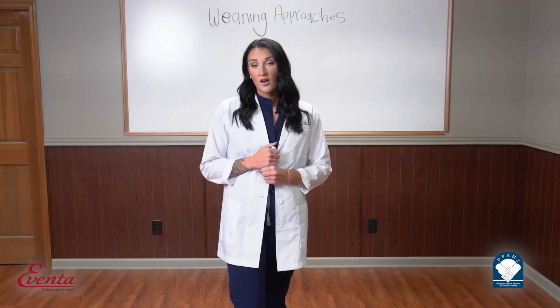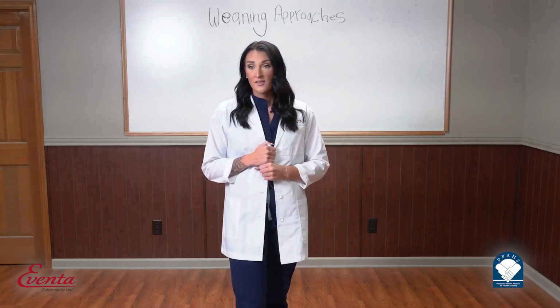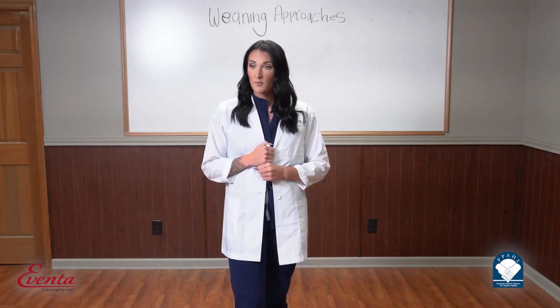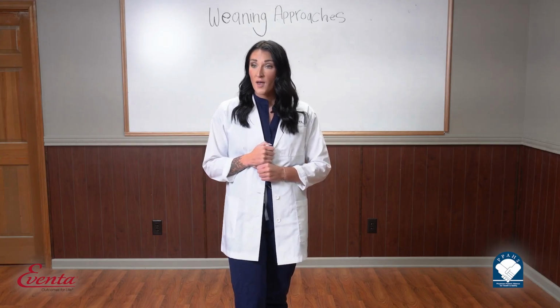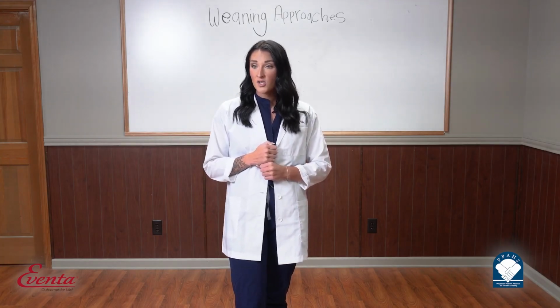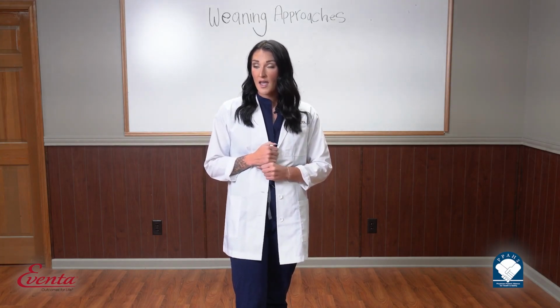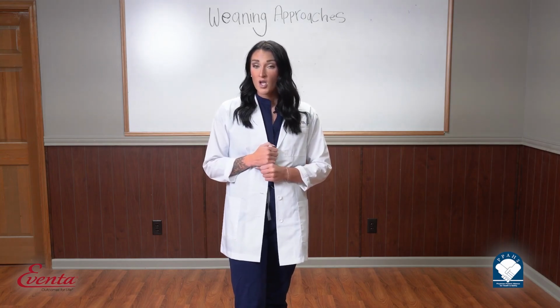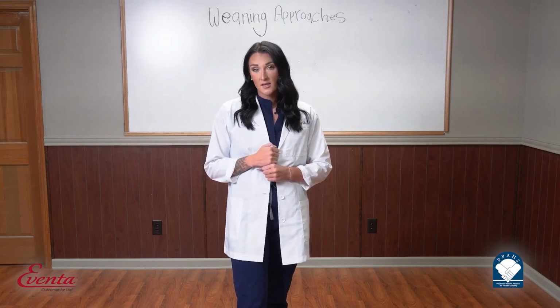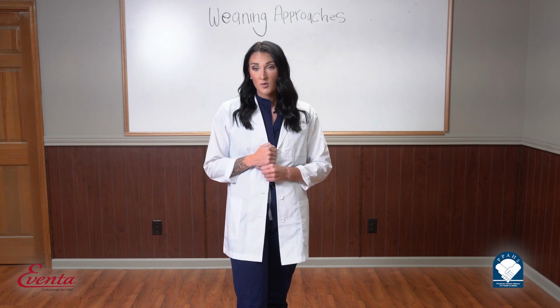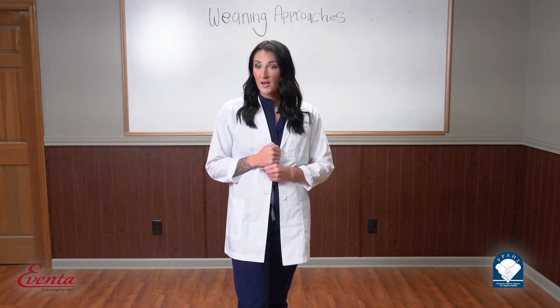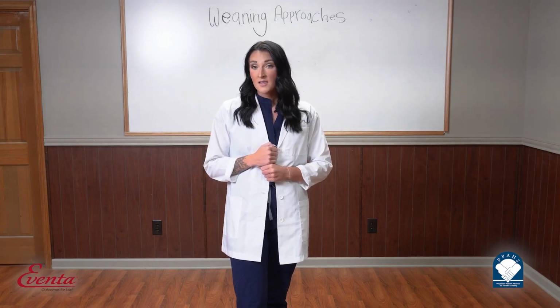You have the average volume assured pressure support. This integrates both volume and pressure controlled ventilation. The IPAP range is set to adjust from breath to breath to meet a target tidal volume. You have your pressure support ventilation. This is the most comfortable mode of weaning for invasive patients and provides supportive care to non-invasive patients.